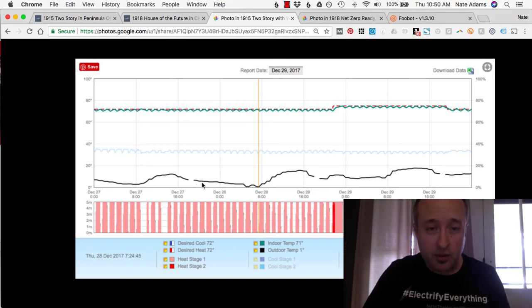But the key thing is, what we have to design for here is 5 degrees outside. And you can see this line here is about 5 degrees out, and then the furnace actually shuts off for a while. So this is 8 in the morning, so the sun comes out and warms the house up some. And then you can also see this period here is also in the 5-degree range down to 0. So this is what's called design load temperatures. Only 1% of the year are we below the design temperature, which for Cleveland is 5 degrees. So what you're looking for are the gaps here. If this equipment shuts off, and this is on low stage, so this furnace is way too big for this house, which we knew, but it didn't fit in the budget to adjust the HVAC.